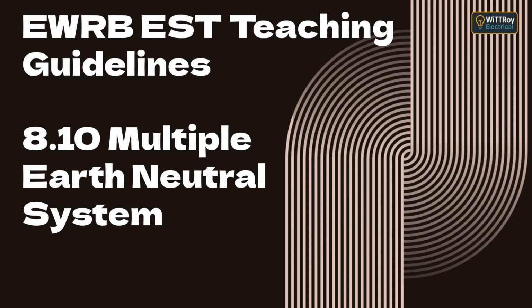Topic D, importance of reliable low-resistance earth circuits. For the MEN system to work correctly, both the protective earth conductor and the bonding conductors must have low resistance. Low resistance ensures that enough current flows during a fault to operate the protective device, usually within 0.4 seconds for socket outlet circuits. If the earth path becomes high in resistance due to loose connections, corrosion, or undersized cables, fault current may not be high enough to trip the circuit breaker. That means the exposed metal parts could remain live, creating a shock hazard. So, always make sure earth and bonding connections are clean, tight, and continuous.